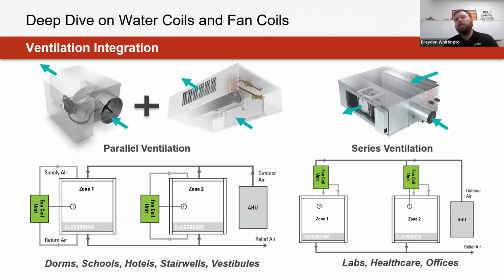But then what we'd also see is options with blower coils for series ventilation systems. What you'll notice here is that you have a blower coil that's addressing both your capacity needs for the space. But we'll also notice this intake or pressure intake valve on here that's almost taking on some of the responsibilities of what we'd see for VAV, throttling how much fresh air is going to be provided to that occupied zone instead.